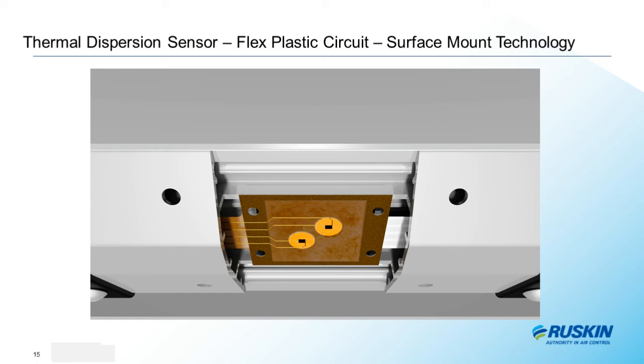We're responding to market demands to eliminate field failures of an entire probe just because one sensor's failed. So now, in addition to the most durable sensors ever made, we have the ability within the supervisor's menu to selectively turn off one sensor without failing the entire probe. With more sensing points, one sensor is less critical. Technology here is so advanced that a failed sensor will put itself in timeout if it's being bad. Greater uptime and higher reliability for your process or building is the result.